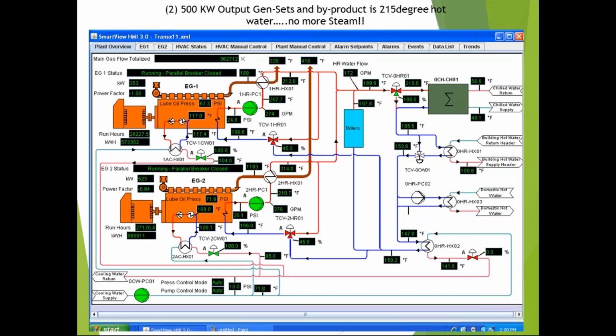Then what happens, this is a plate and frame heat exchanger. If I have too much heat going back to the engines, I dump it through cooling towers, but I'd really never do that because if I am doing that, I'm setting something up wrong, meaning as an operator. I use so much energy to get this heat, and now I'm dumping it out of cooling towers. That's something where, again, something's wrong operationally. Then I send the jacket water back. So now it's at, what is it at? 150 degrees, right? Now I'm sending it back to the engines.